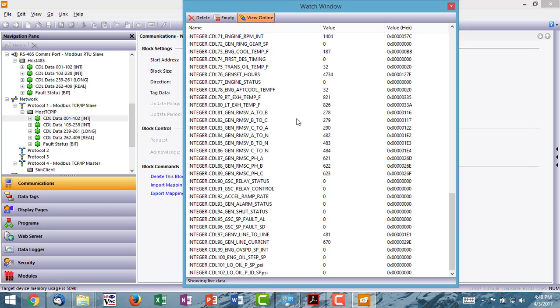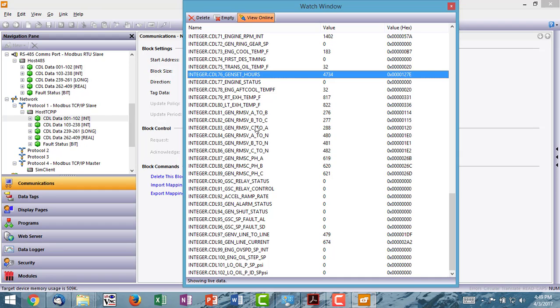But the data that you do see will help you validate with the genset. So now I can compare this number, 4734, to the actual genset panel to determine if that value is correct.